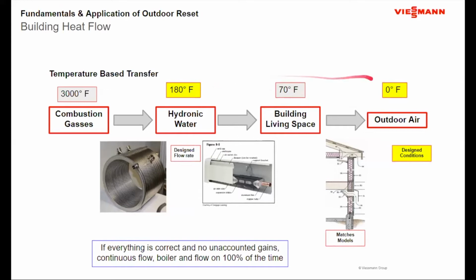But here, I've now chosen 2 of my design conditions when I'm looking for the setup of my system. On the design day, which I've identified at 0-degree outside temperature, I need 180-degree water based on the heat loss of my building, based on my flow rate, and based on what I've chosen for a heat emitter and how much of that heat emitter goes into the building. Now, additionally, based on this selection of 180-degree, little side note here, I've now also looked at how efficient, I've really set the yardstick of how efficient the heat transfer can be from my combustion gases into my hydronic water inside the heat emitter inside the heat exchanger of the boiler. So not only am I affecting comfort in my decision here, but I'm also affecting efficiency.